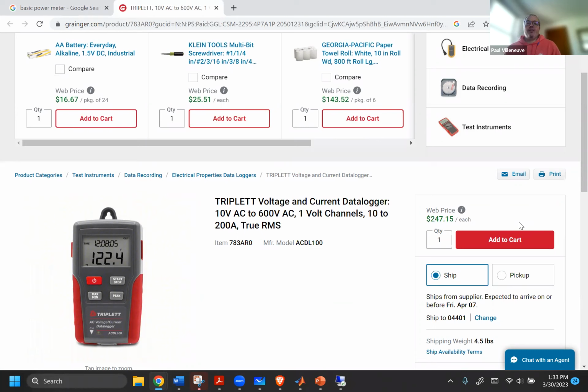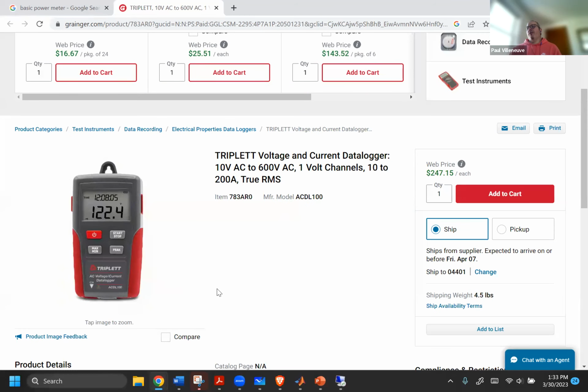Yeah, that's literally, you just set it up. You measure voltage across whatever you're trying to determine the power consumed. You measure the current in, and you're good to go. The other thing you have to be careful about with phase shift is that if you measure the phase shift, that's just the angle between the voltage that you apply and the current. So sometimes it can confuse you to say, hey, my voltage is this, my current is this, so this is the angle of the current. That's not necessarily the angle of the current. It depends on where your angle of zero is going to be. So sometimes your voltage is not at an angle of zero. So sometimes you can get yourself into a little bit of trouble if you haven't considered where your reference voltage is, that's the one at an angle of zero.